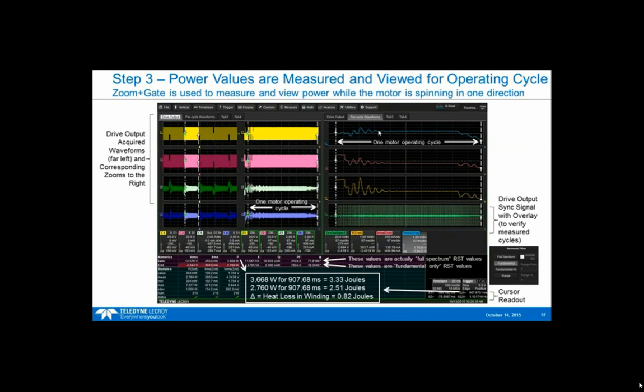This is our RMS voltage, RMS current, and power plotted over time. By gating, this numeric table is only showing power values calculated on the zoomed and gated area, which is one operating cycle. I have time information from my cursor readout right here. So there's one cursor, there's another, and the delta between the two of them is this amount of time. From this power value and this time value, I can calculate the amount of energy, the joules.